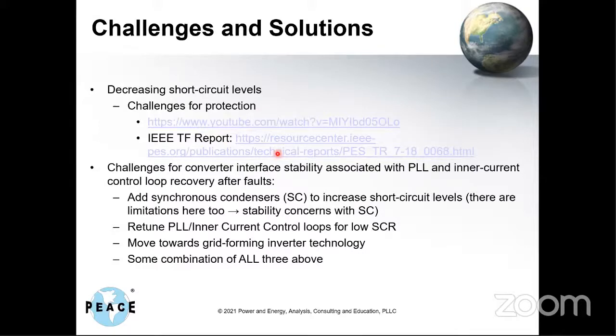The other thing with protection is distinguishing between balanced and unbalanced faults. That's one of the reasons you've probably heard there's now talk, and certainly in Germany they've started doing this, of asking converter interface generation to actually provide negative sequence current during the fault.